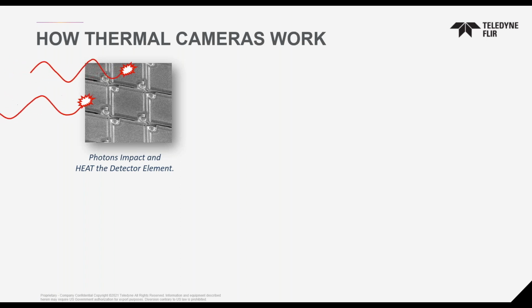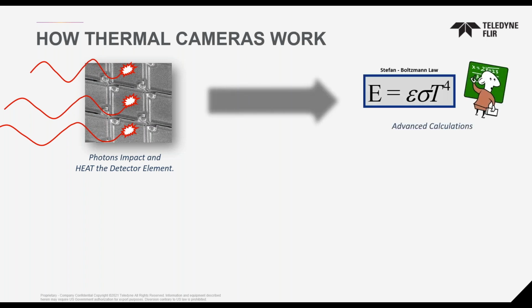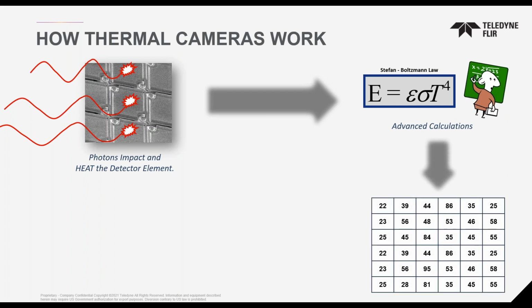What's happening here is we're talking about heat radiation detected on the sensor. We use calculations, the Stefan-Boltzmann law, to define the measurement values, producing a temperature range or measurement for each pixel on the camera, associated with its sensing ability. This heat sensing gives very precise, quantified values, allowing you not only to monitor thermal performance but also identify and evaluate the relative severity of heat-related problems.